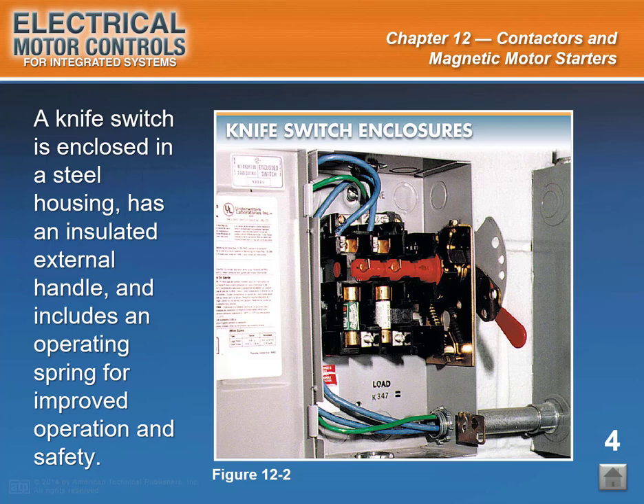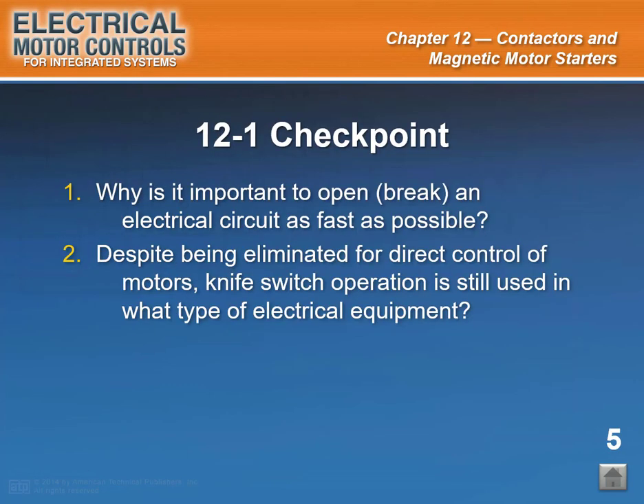Also, an operating spring was attached to the handle to ensure quick opening and closing of the knife blade. The switch handle was designed so that once the handle was moved a certain distance, the tension on the spring forced the contacts to open or close at the same continuous speed each time it was operated. End of Slide 4. Start of Slide 5.